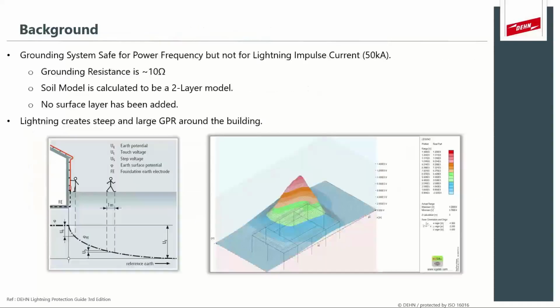Now, if we look at that same grid that we want to adjust, as I said, we're going to inject 50 kA of first negative lightning stroke current. The grounding resistance we calculated previously for this was around 10 ohms, which is also the benchmark, or the target, we try to hit when we design lightning protection systems. The soil model was calculated to be a two-layer model, as shown previously as well. And in this case, no soil covering layer has been added yet, so no substation gravel or any insulating material has been added yet.